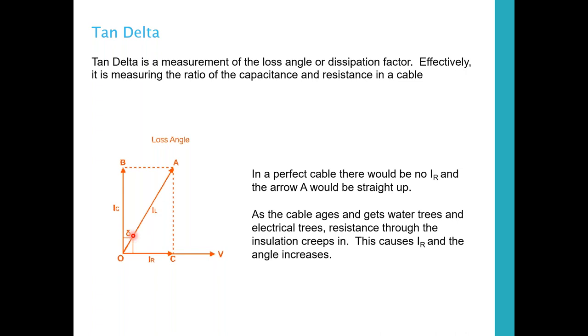Very similar to power factor. Anyone who's done any power engineering, very similar to looking at where your power factor is, so power factor rating on a transformer and all that, you're looking at very similar concepts. Slightly different, but if you understand the one, you'll understand what the tan delta test is looking for. And you're really just looking at your leakage current from your conductor through your insulation. And that's what your IL is, your leakage current.